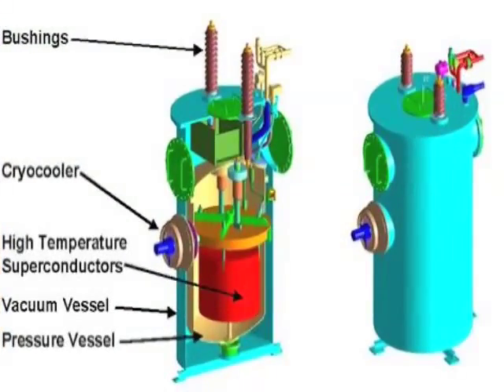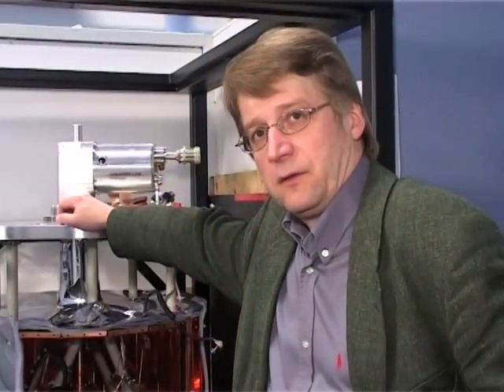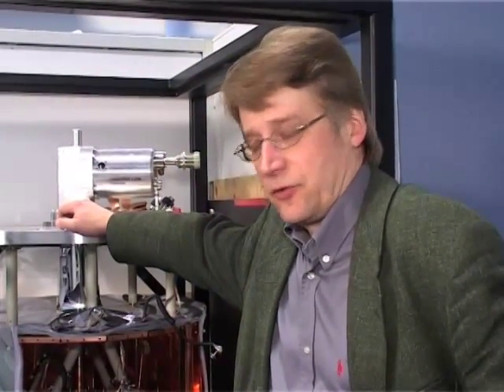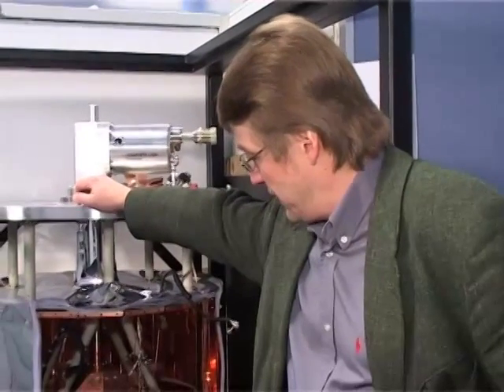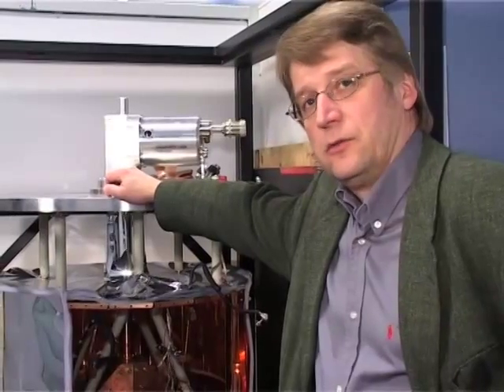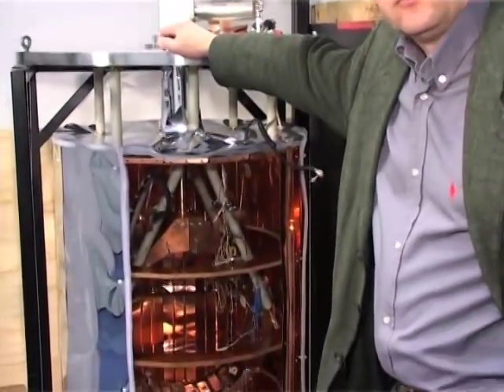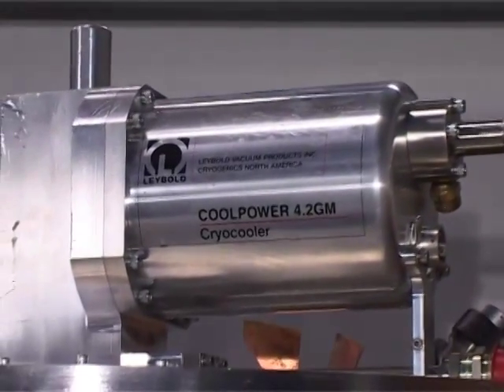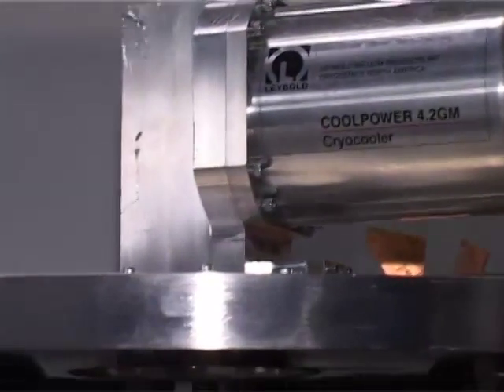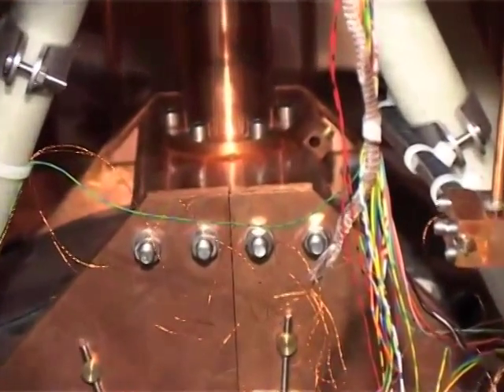This is so-called micro SMES. It is purposed for power quality applications. We have some commercial SMES units which are based on niobium-titanium technology. But this magnet has been made from niobium-tin. So that means that we don't have to cool it down with liquid helium. So we can use efficient cryocoolers which cool the magnet down to 10K. Here you can see the cryocooler unit which goes down to the magnet.